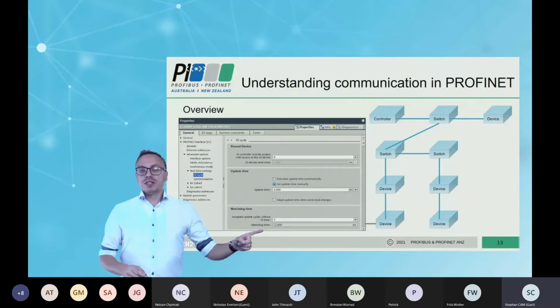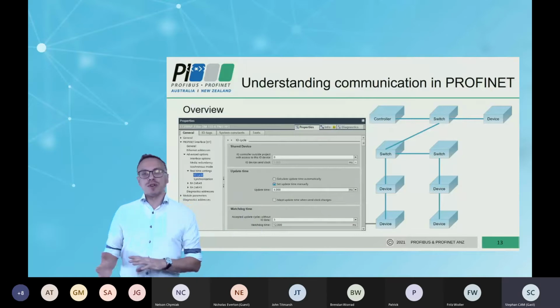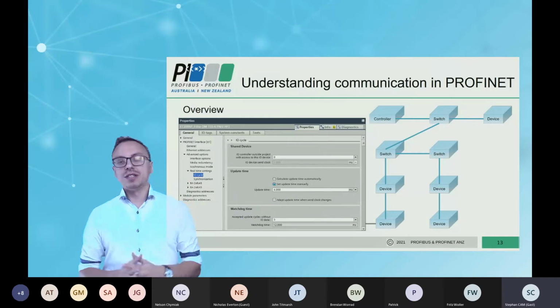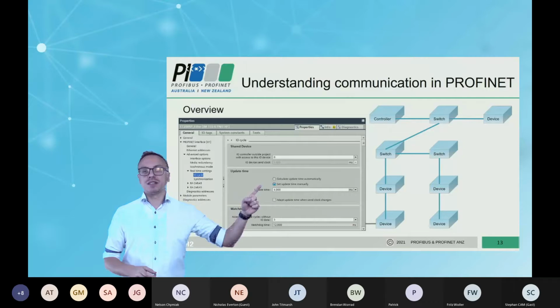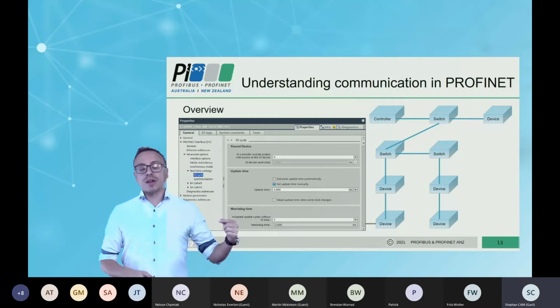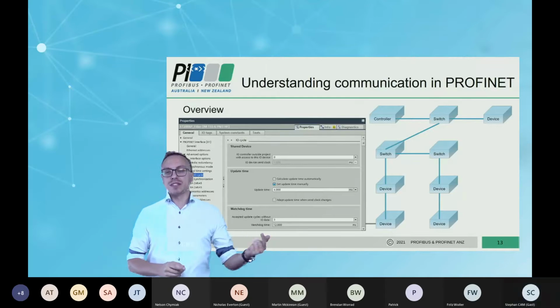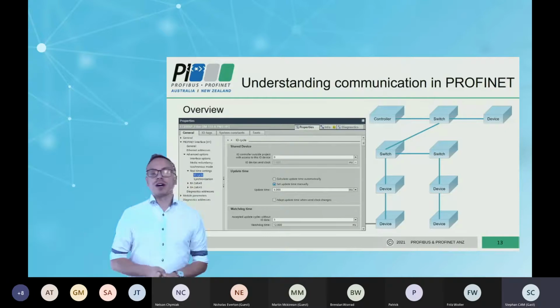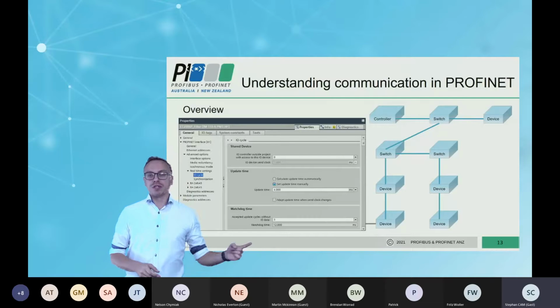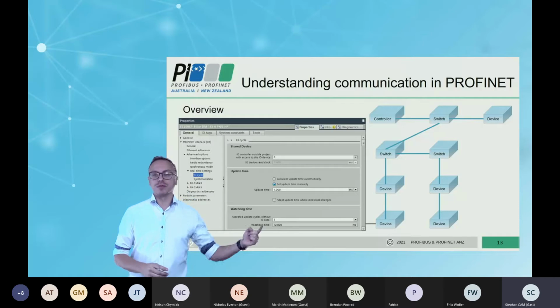The watchdog time means how long the PLC or the devices will wait for this information. For example, if the PLC doesn't get information from this node within the watchdog time, it will try to parameterize this node again. From the other side, the device will do it the same way. So if the device doesn't get new output information within 12 milliseconds, the device will drop off. This is what the watchdog time describes. Important: please don't touch the watchdog time if you don't have a condition monitoring system, because this 3 times the update time is normally enough for your process.